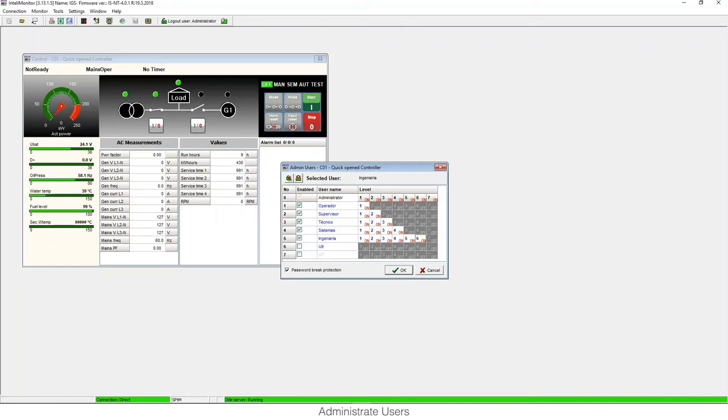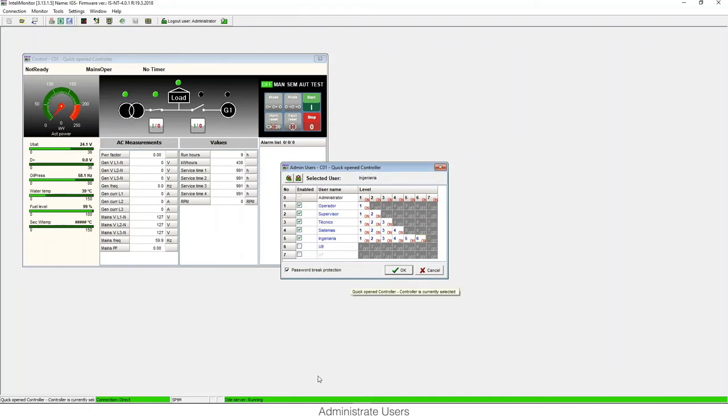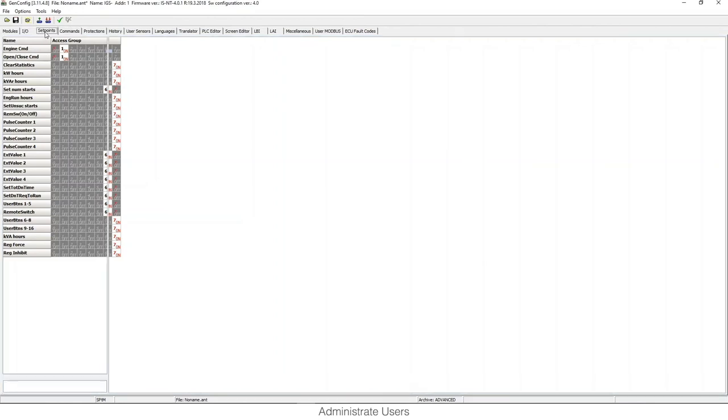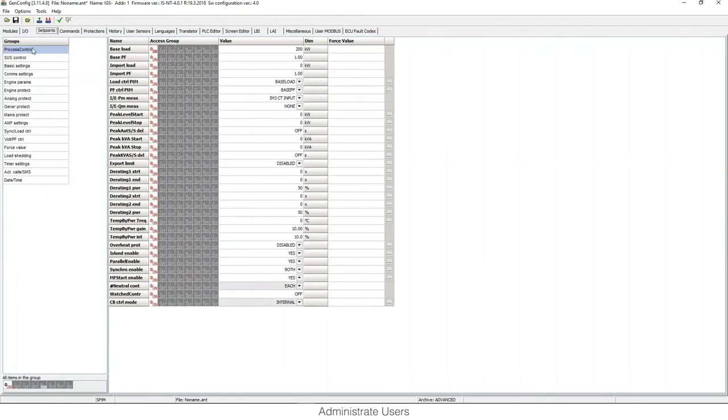The access level is required for modifying set points, statistics, or control commands. We need to modify them in the configuration using the software tool GenConfig that I have open here. In the tab commands, we can choose which kind of commands and statistics need to have special access. They need to be logged in to be modified.